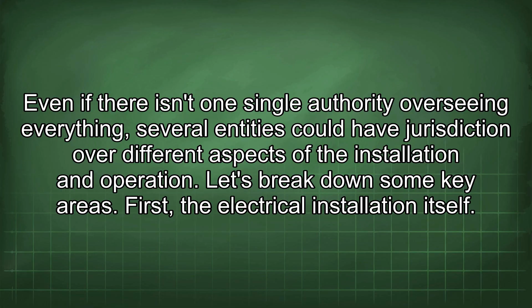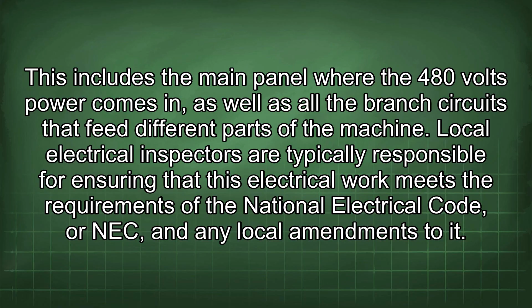First, the electrical installation itself. This includes the main panel where the 480 volts power comes in, as well as all the branch circuits that feed different parts of the machine. Local electrical inspectors are typically responsible for ensuring that this electrical work meets the requirements of the National Electrical Code, or NEC, and any local amendments to it. This means checking things like proper wiring methods, grounding, overcurrent protection with circuit breakers or fuses, and ensuring that all the equipment is properly rated for the voltage and current it will be carrying.